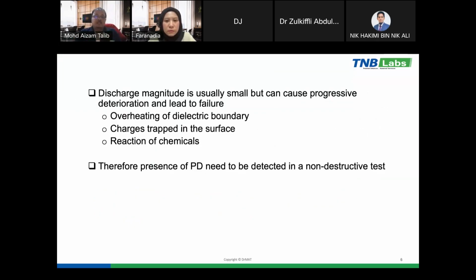So the discharge magnitude is small, but as I said, it can further deteriorate the insulation system of the equipment and finally lead to the failure of the entire equipment. Among the factors that can cause partial discharge are, for example, the overheating of the dielectric boundary, a charge trap on the surface of the insulation, and also chemical reactions. For example, in the transformer, we have oil, and the reaction of the oil with steel and other materials will create a partial discharge. Therefore, the presence of partial discharge needs to be detected in a non-destructive test.